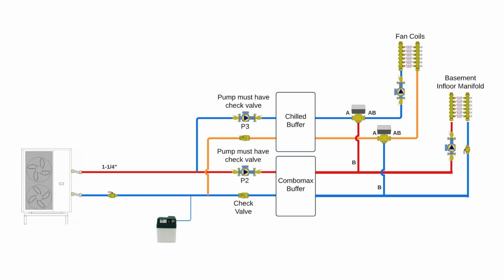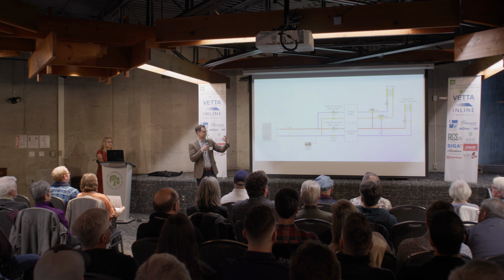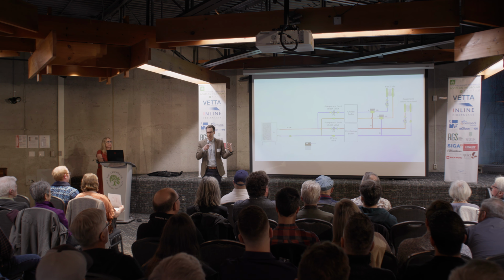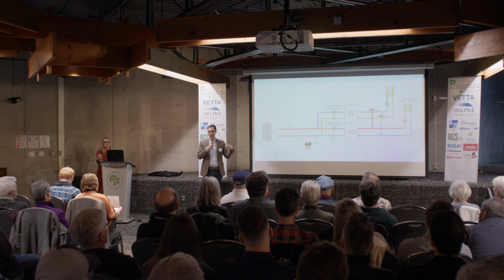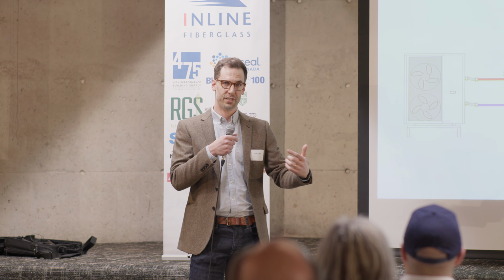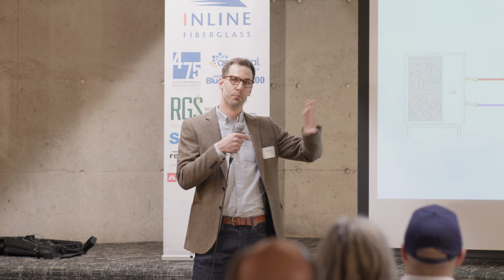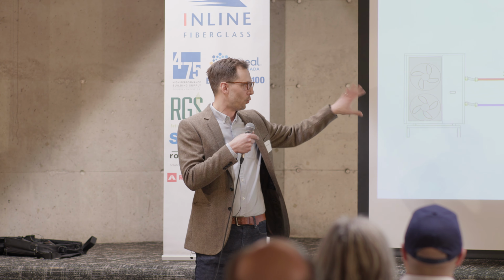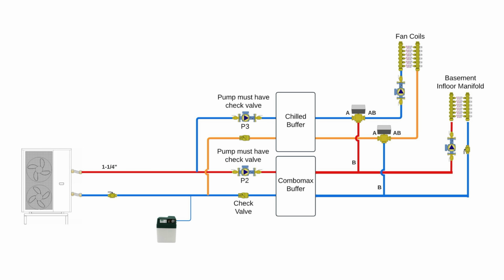So in heating season, we're making hot water and sending it to that buffer tank on the bottom, and it's trying to maintain a temperature. And then the pumps on the other side of the diagram are pulling heat out of that tank and sending it to the in-floor heating in the basement and up to the fan coils on floors 1 and 2. That buffer tank also has a copper helical coil in it, and the tank is full of a glycol water mixture that's kept hot all the time. And then the domestic water, when someone takes a shower, goes through that coil and gets preheated and then put into a final electric tank. So this one outdoor unit is doing all of the home heating, most of the domestic water heating, and all the home cooling as well.